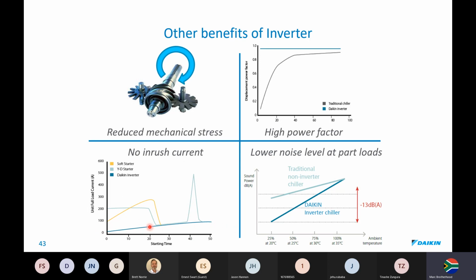There's no power spikes. So if you look at this chiller for likeness, if we had, say, three 100 kilowatt chillers, if I selected a soft starter on this chiller, which would be pretty much a part wound start and run motor, you can pull up to 300 amps. If you have a star delta starter, you're going to pull around 200 amps, then drop as you go into delta range. And then you're going to peak as your inrush current, as your magnetizing current would possibly pull in.